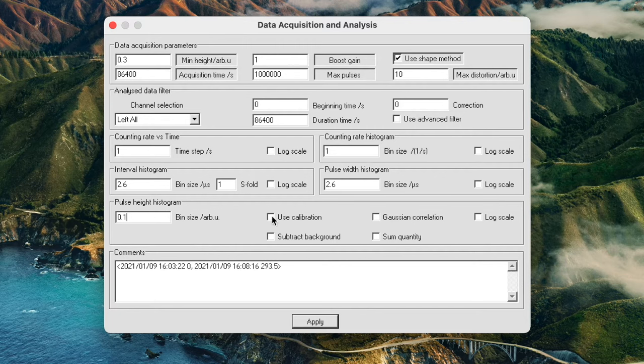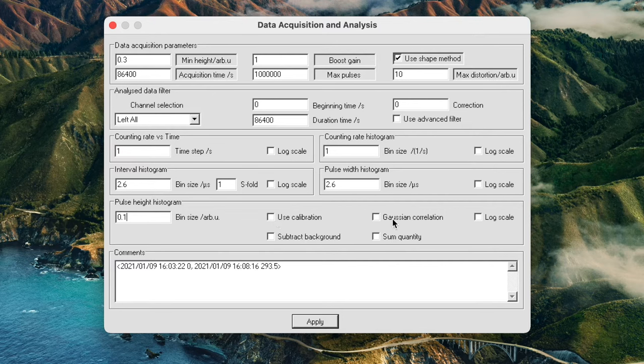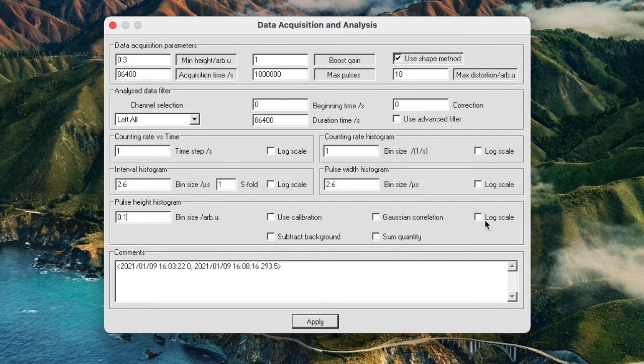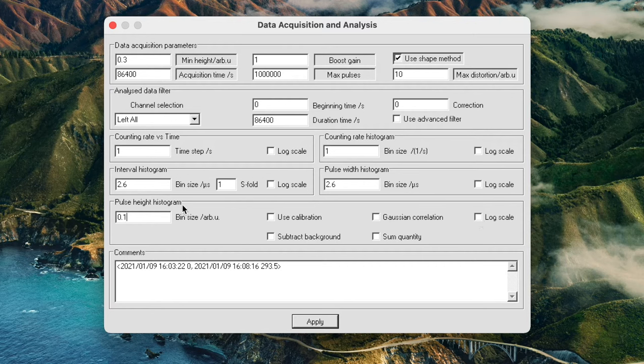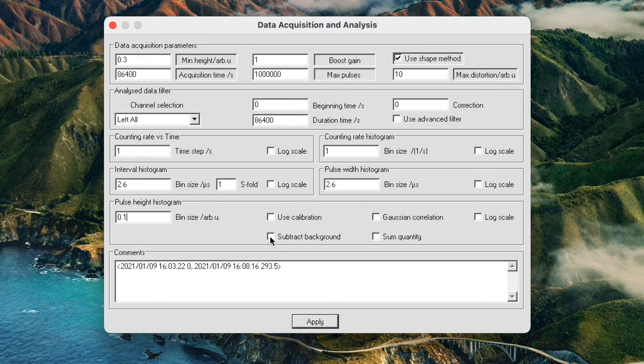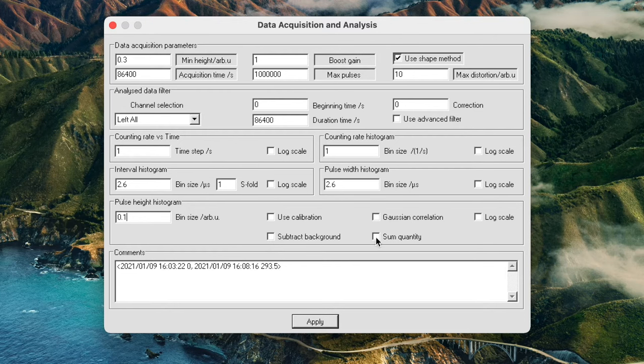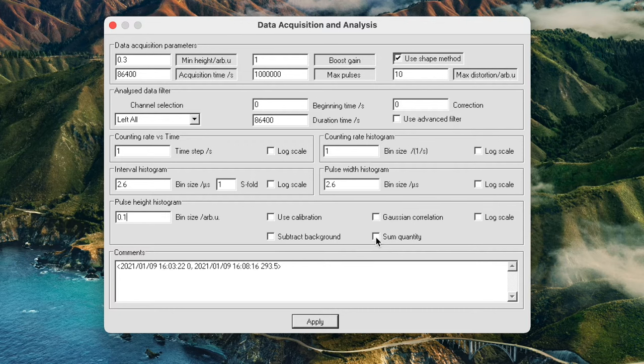These tick boxes are as described here. This one is if you're using calibration, this one is if you're using the Gaussian correlation which we will explain later. This one converts your graph to log scale, this refers to the pulse height histogram. There's also a background subtraction feature which I will probably cover in another video. And this one here gives you the sum quantity which is another way of saying it converts the pulse height histogram to energy per bin rather than counts per bin and I find that feature quite useful.